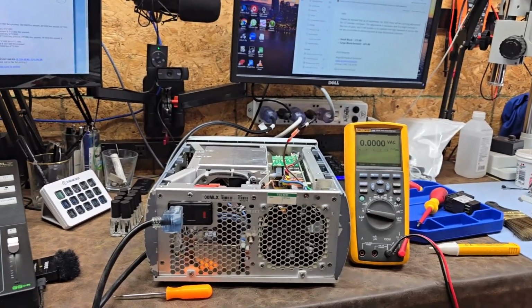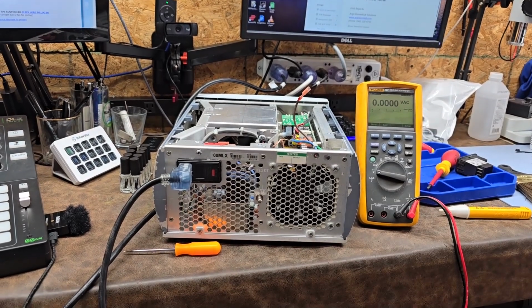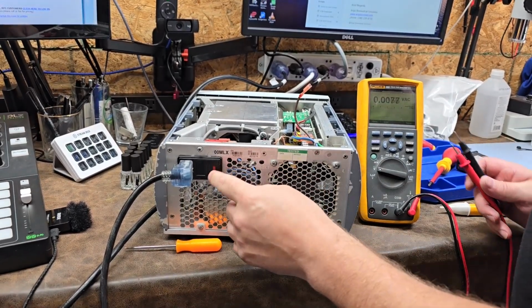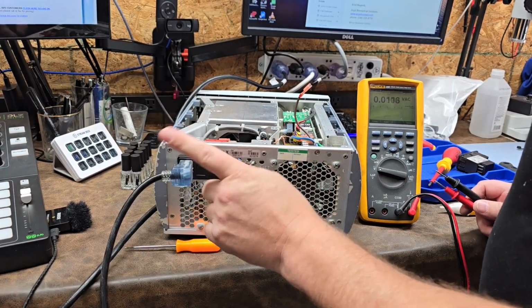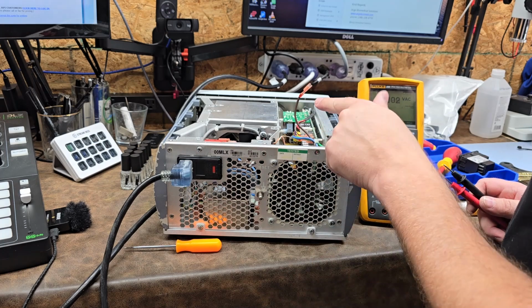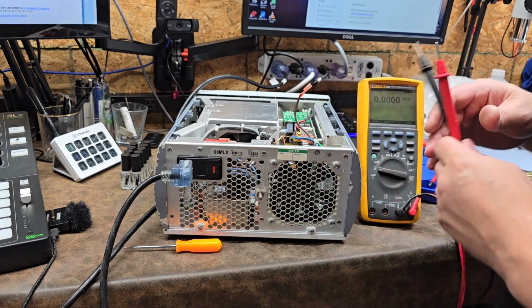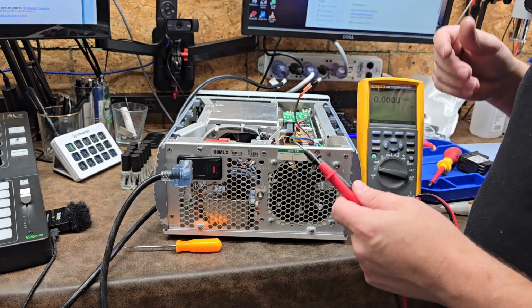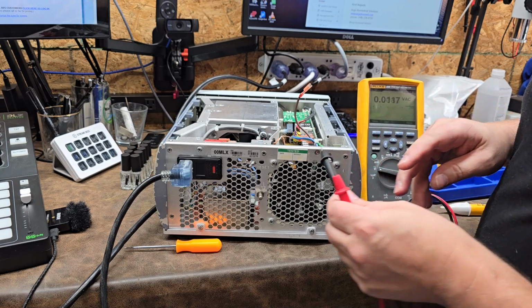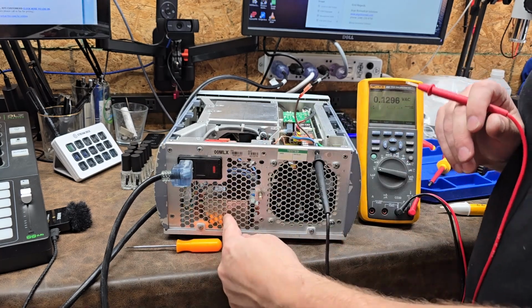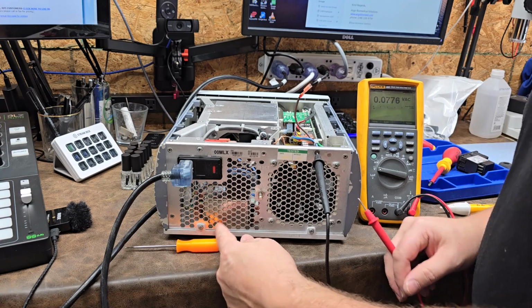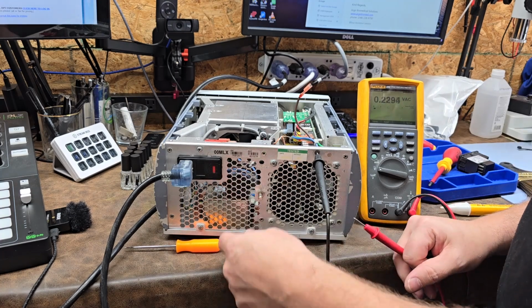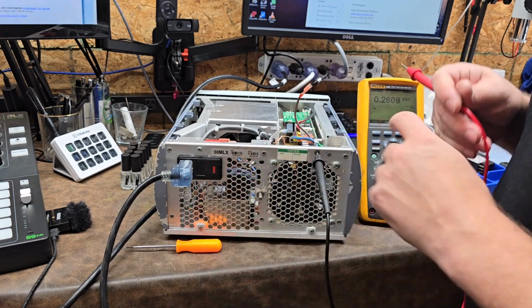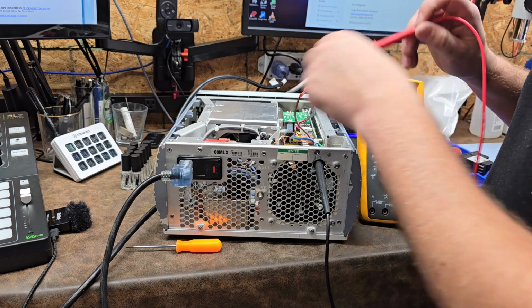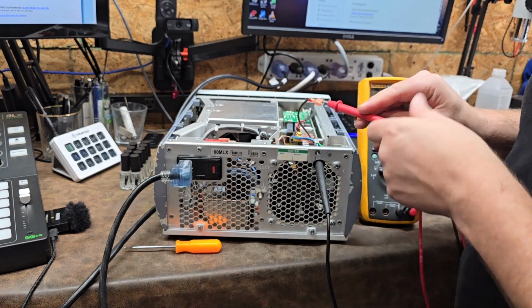Okay guys, here we go. I have the unit currently set up with the brand new 6.3 amp fuses, and the power is connected. I have the hot lead off of the main PCB, and we're going to check and see if we have power and if it's going to pop a fuse. If it pops a fuse, then that means we have a defective AC filter or maybe a defective AC input module. We don't know that yet, so let's go ahead and connect our multimeter up here to our lead.